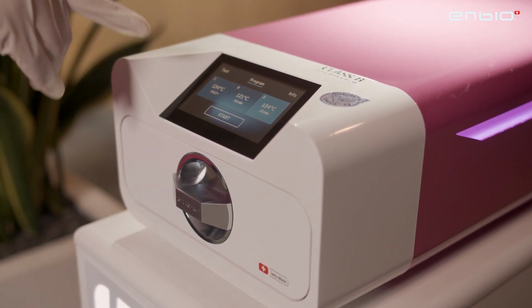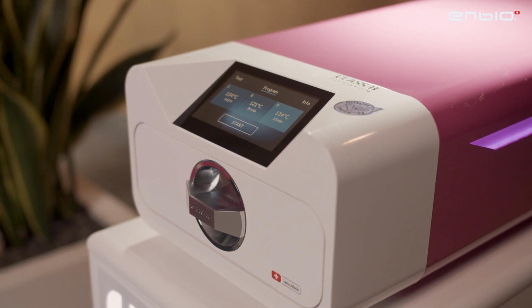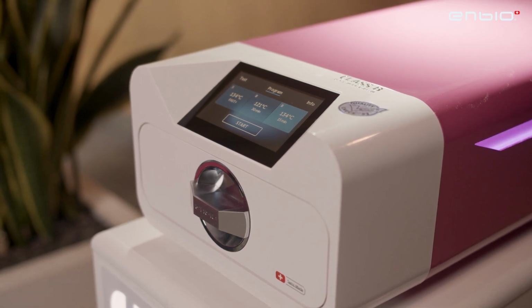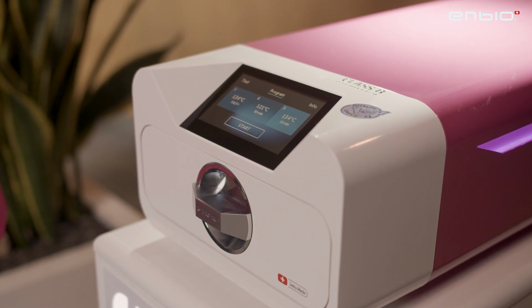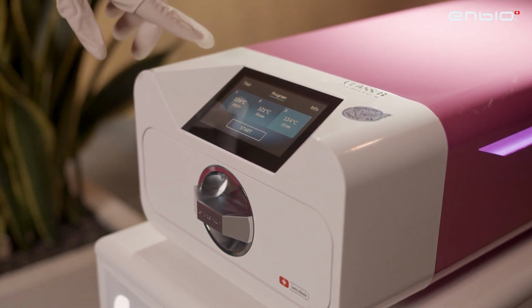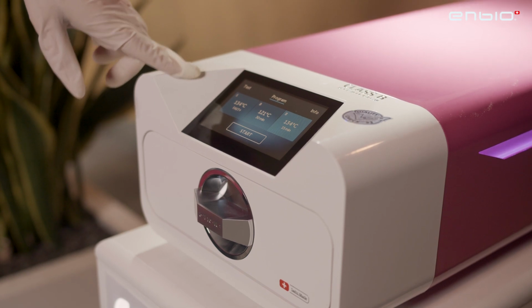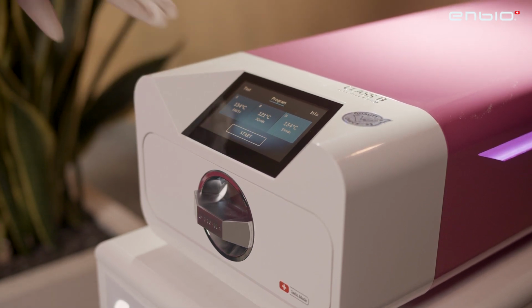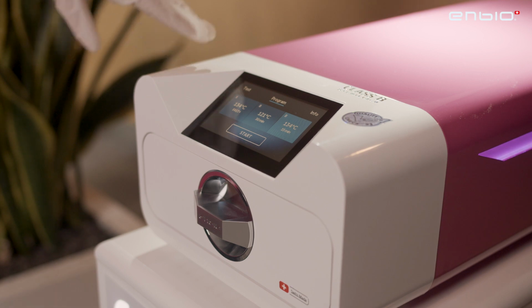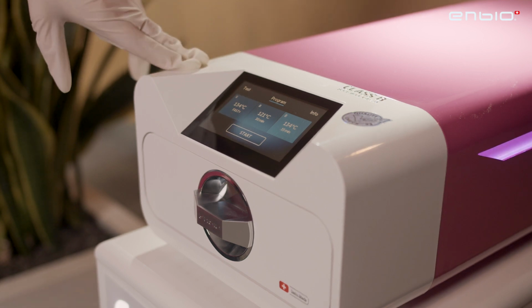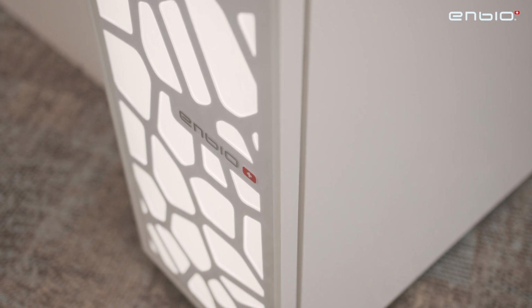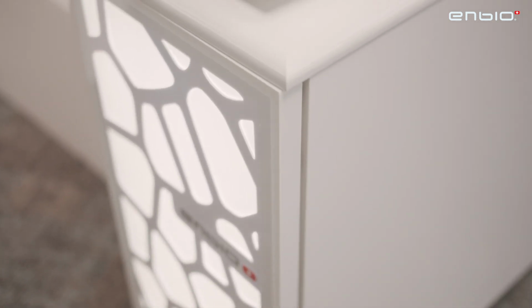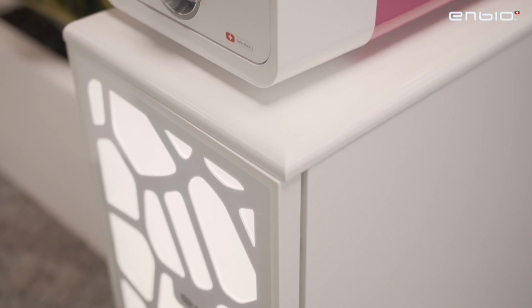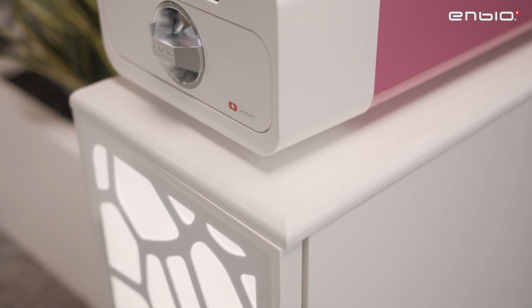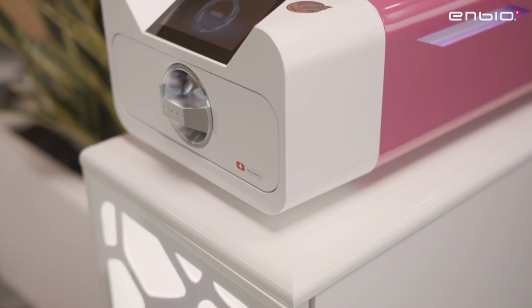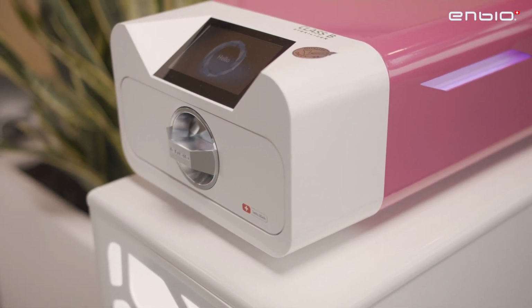As we can see here, first we have the fast program. It sterilizes the tools at a temperature of 134 Celsius degrees, and it is a Class S sterilization cycle. So it is important to know that this program does not include the drying stage, so we should always use this program when we want to sterilize solid tools, and it is important to remember to sterilize the tools without the pouches, because otherwise the pouches will be humid.